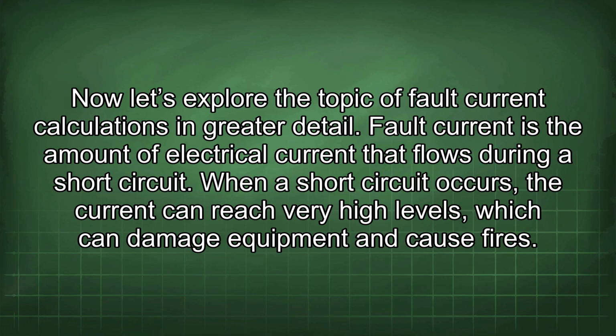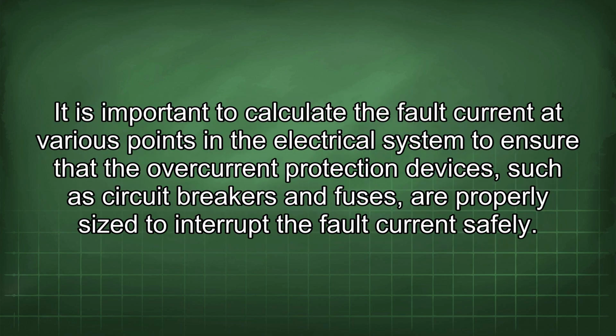Now let's explore the topic of fault current calculations in greater detail. Fault current is the amount of electrical current that flows during a short circuit. When a short circuit occurs, the current can reach very high levels, which can damage equipment and cause fires. It is important to calculate the fault current at various points in the electrical system to ensure that the overcurrent protection devices, such as circuit breakers and fuses, are properly sized to interrupt the fault current safely.